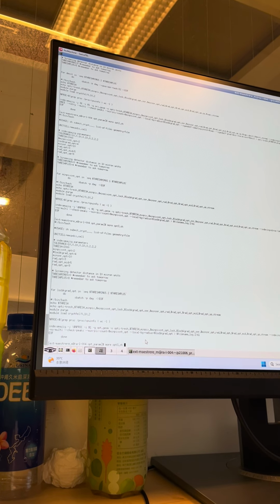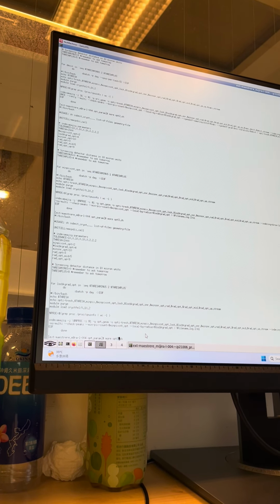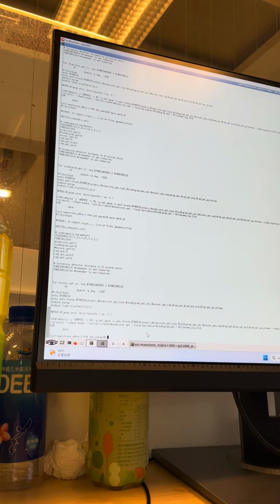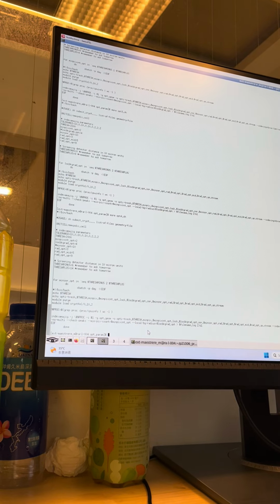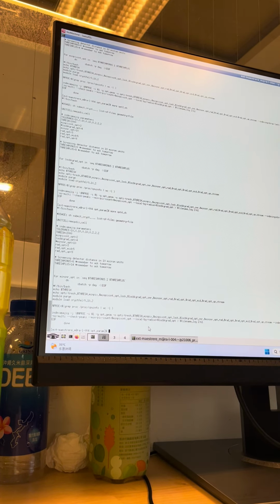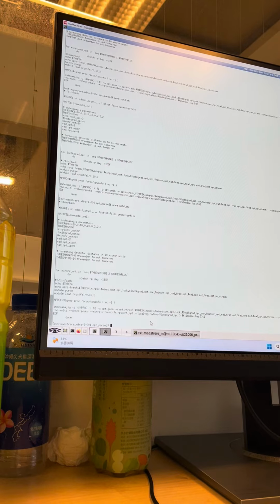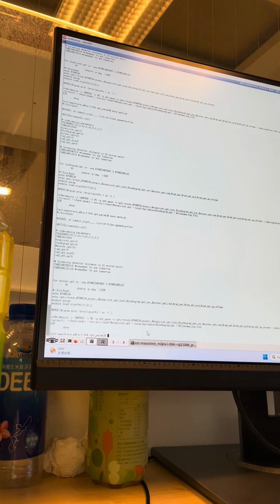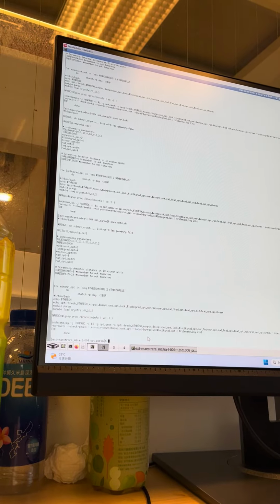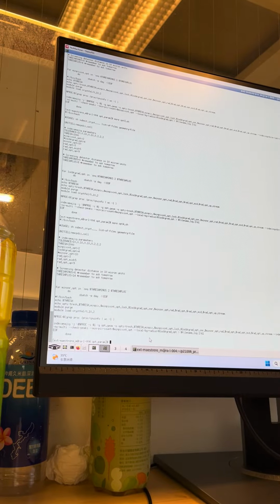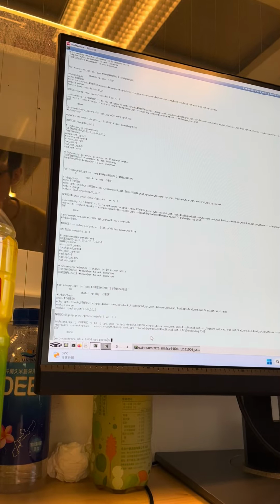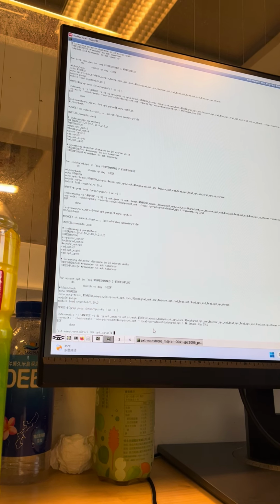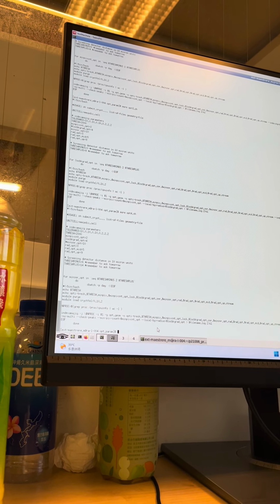Then you're going to look at opt 4. And in opt 4, it's removing min-SNR. And so min-SNR is now going to run from 6 to 14. Sorry, I didn't explain min-SNR. SNR is signal to noise ratio. That means that a peak will only be accepted if it's at least this much stronger, 6 times stronger than the noise.